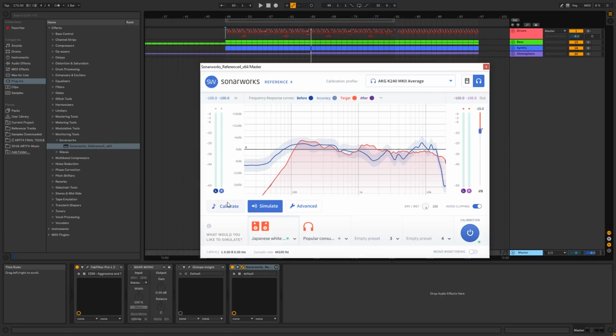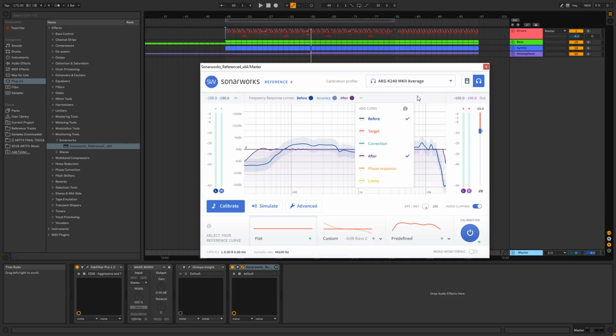Now, I usually just stay in the calibrate section and keep it on flat, and you can see that red line, that's what we're trying to achieve. Now, I'm going to turn the target line off, and now I want you to look at just the purple line here. That's the after. So that's what the calibration is actually doing. After the calibration, that's what we're getting, and that's much closer to a flat frequency response if you compare it to what it used to be.